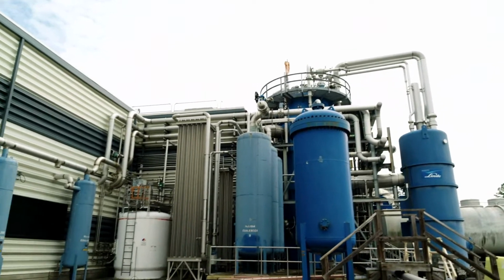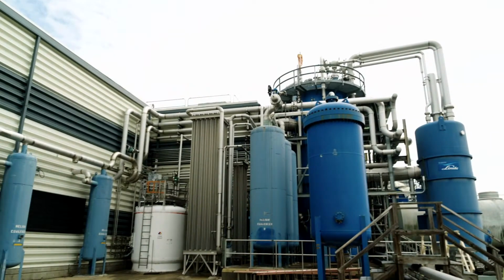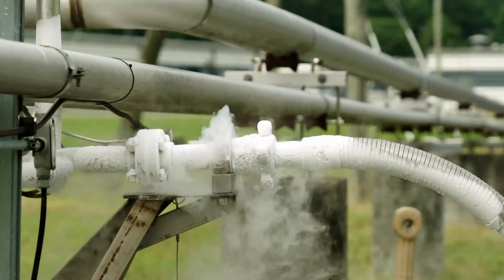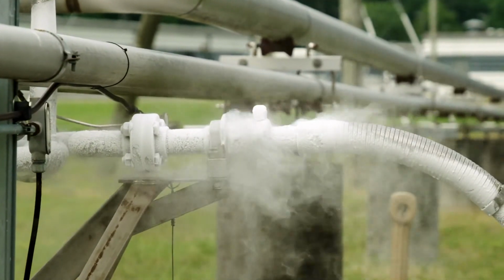Behind me, you see the first refrigeration equipment where the helium is changed in temperature from room temperature, or about 70 degrees Fahrenheit, down to about liquid nitrogen temperature, which is around negative 320 degrees Fahrenheit. Once the helium is at minus 320 degrees Fahrenheit, we're going to move it to the 4.5 refrigerator, which we're going to go see now.